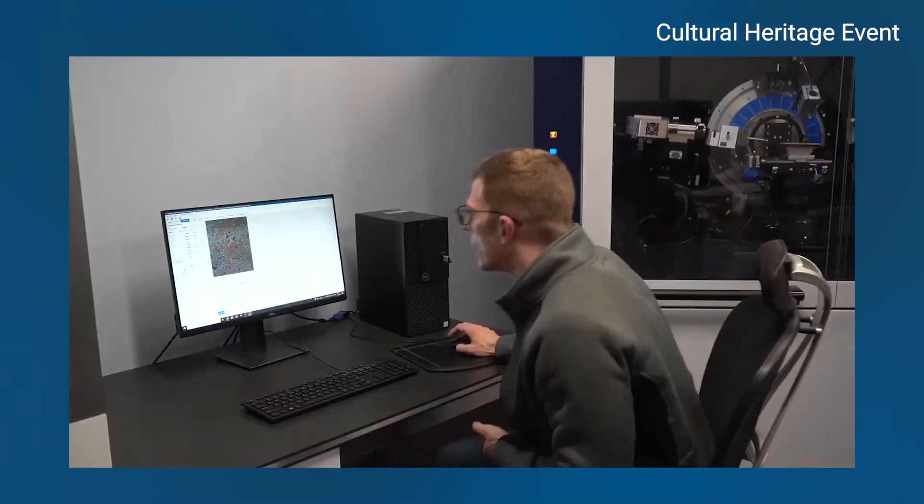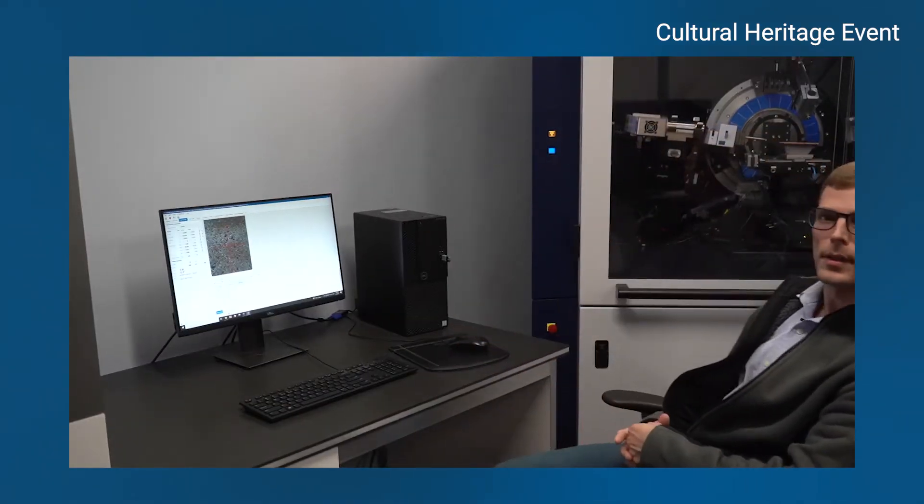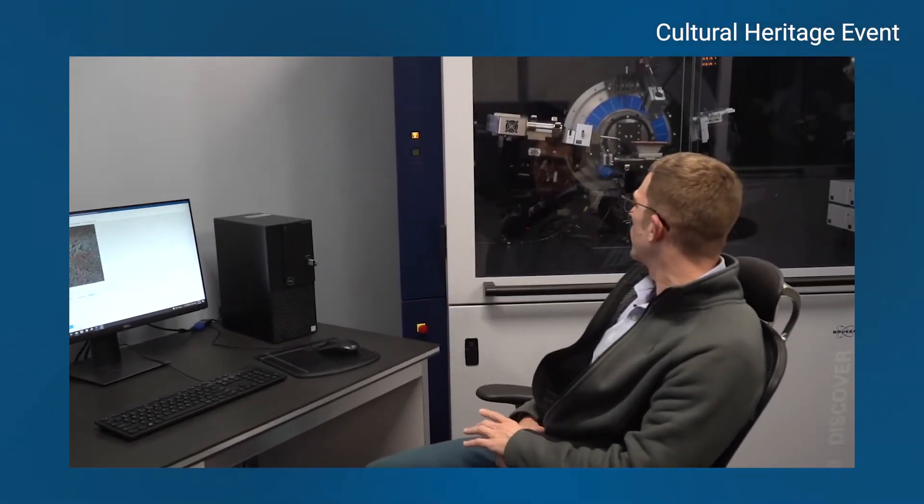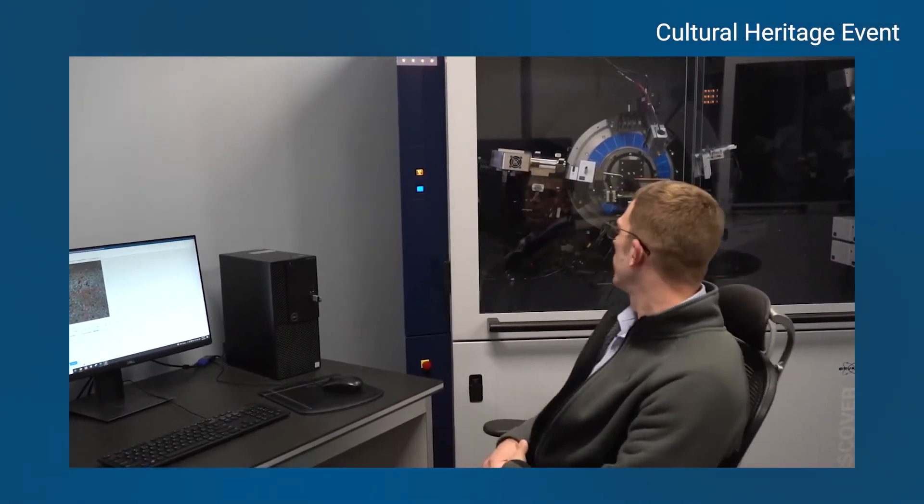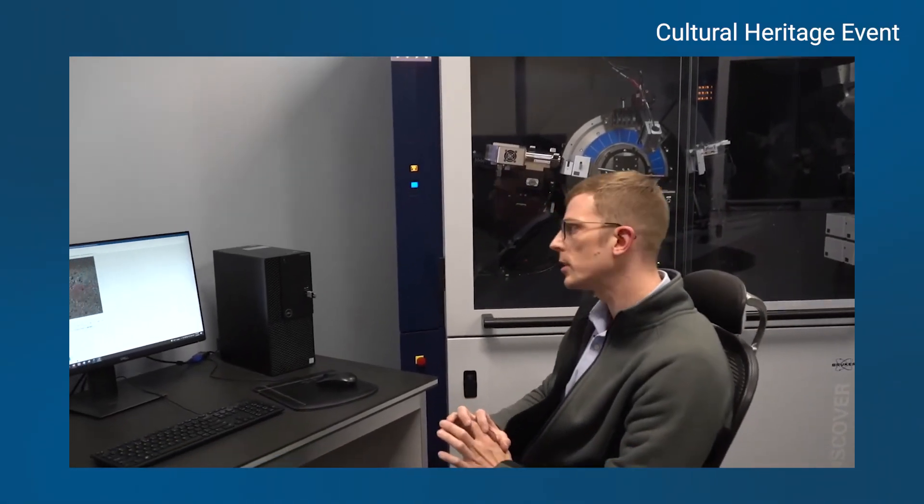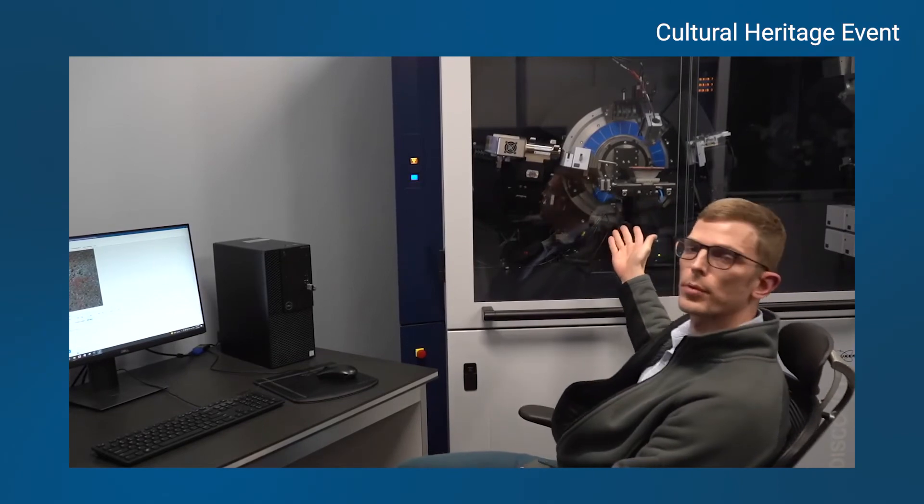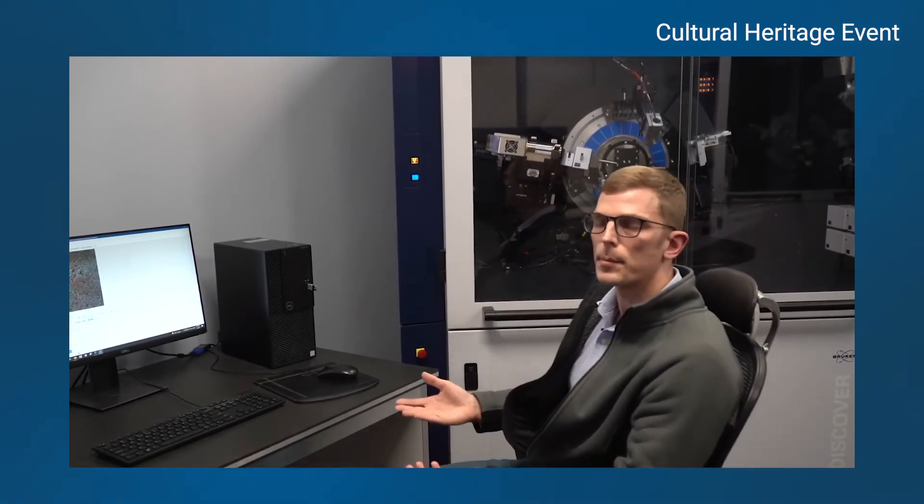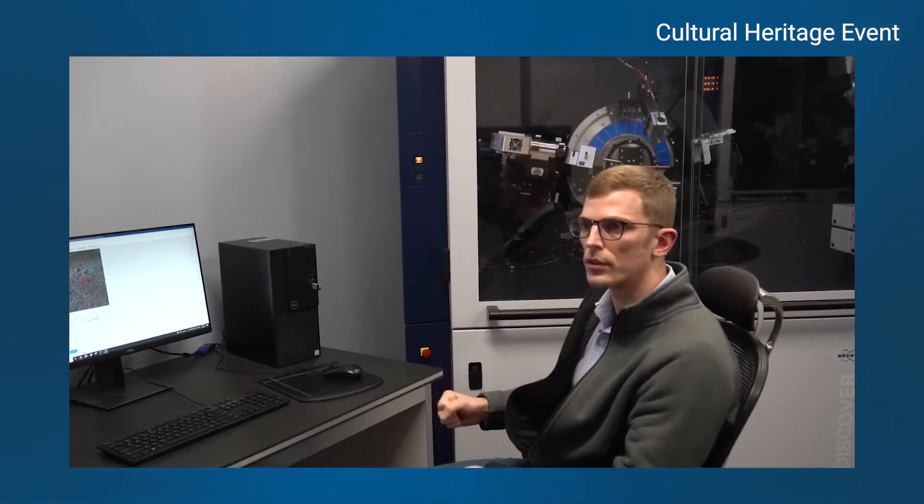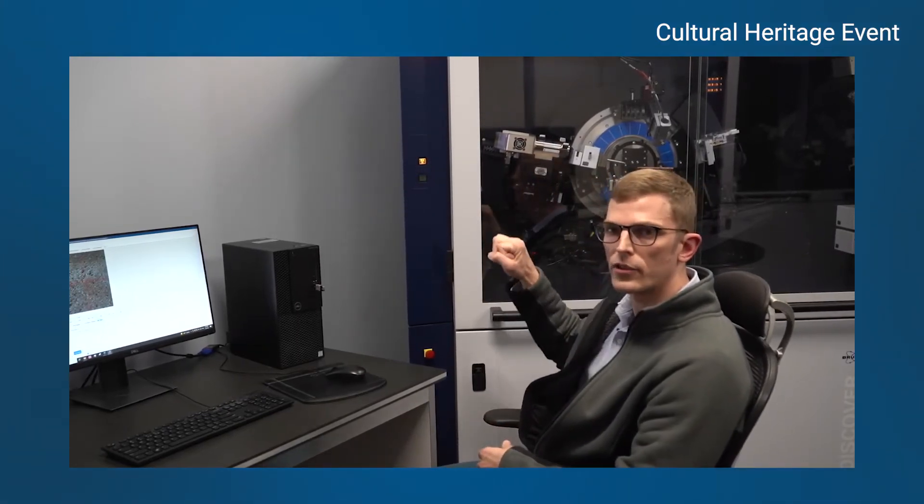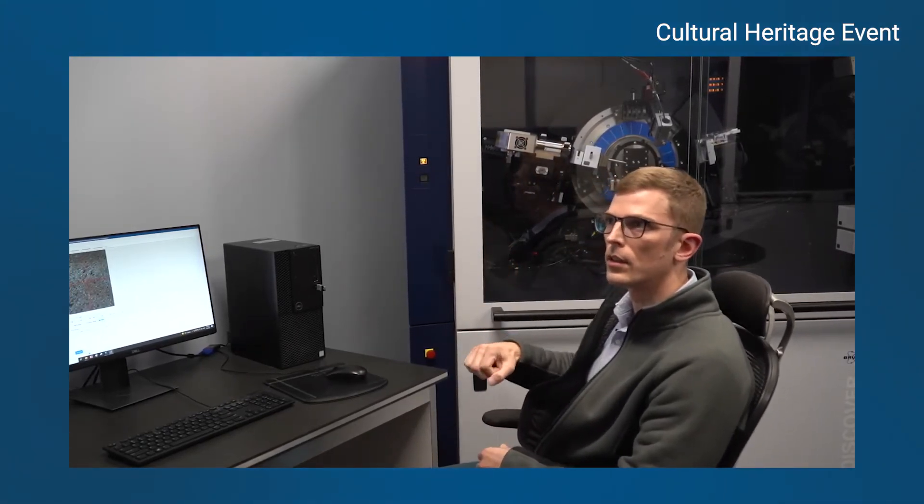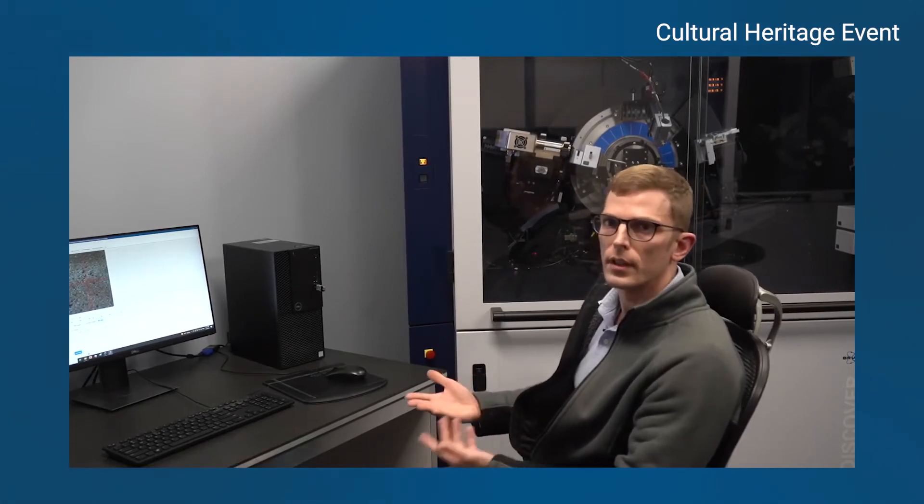So while we're waiting for this image to appear, I should point out, I mentioned this is a spot beam. You might be wondering how big is the spot. For this particular source, the maximum spot size is 2 millimeters, but then we have different collimators you could put in front. Depending on the sampling volume you're going for, the feature size that you're looking at, you can have different size collimators to cut the X-ray beam down so there's only information coming from that feature in the surrounding area.